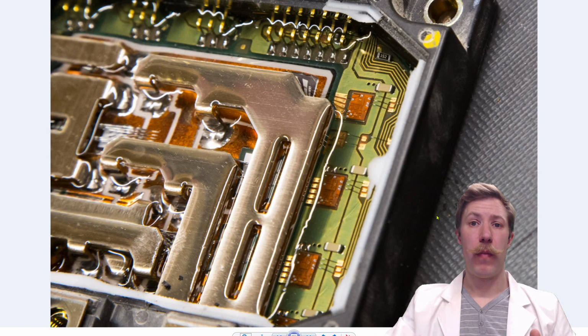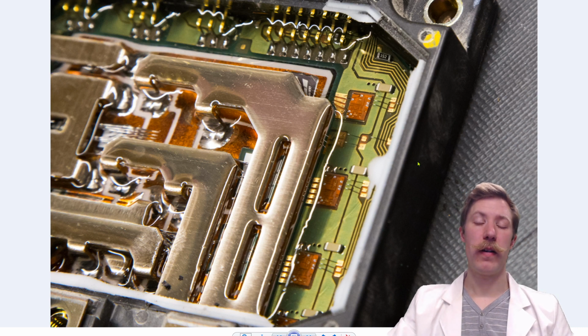The pre-driver part of the IGBT, which are the small brown bricks we can see here, have several different jobs they can do. They can detect overcurrent, undervoltage, overvoltage, and direct die temperature. So let's take a closer look at how these legs up here connect down to the different pre-driver ICs, which are built into the PCB here.